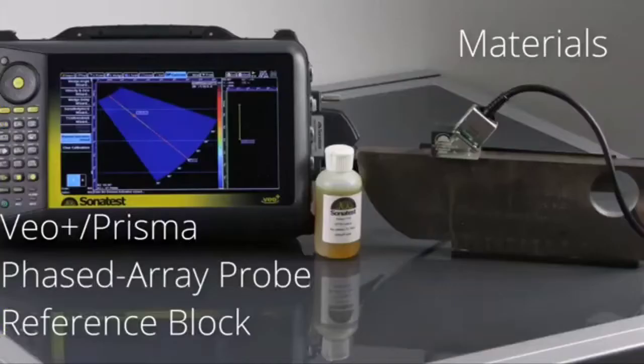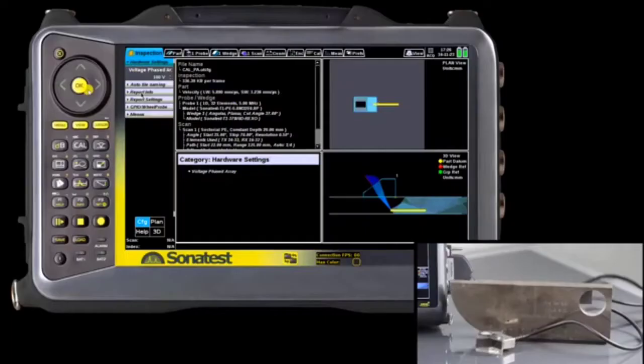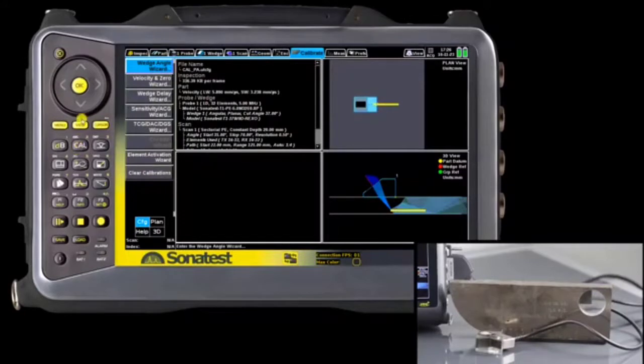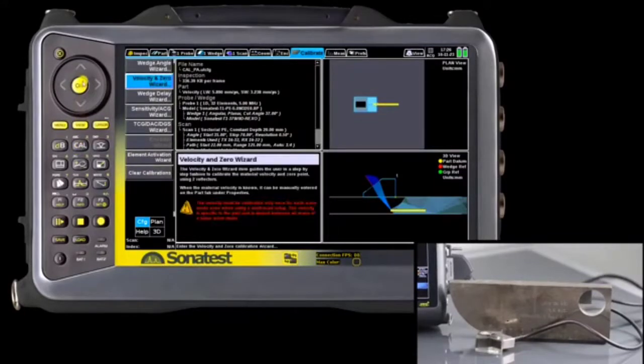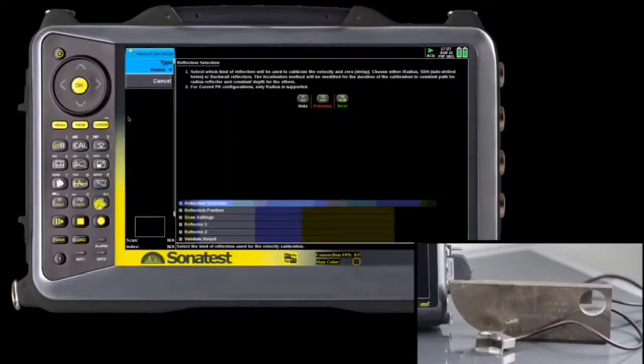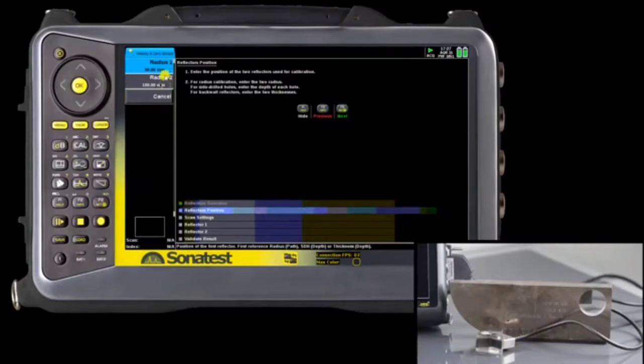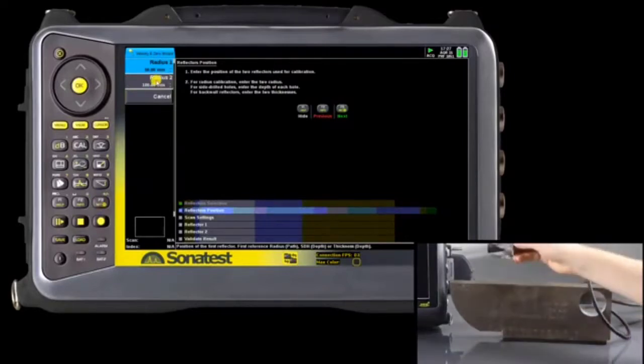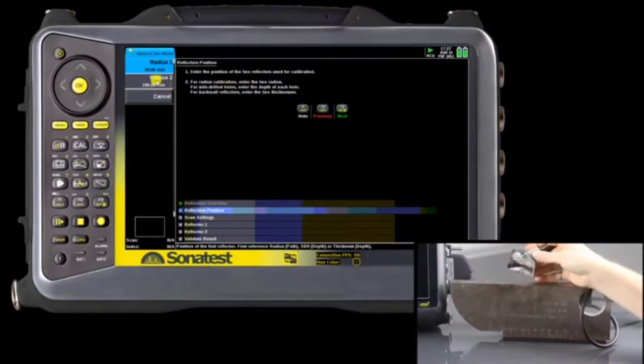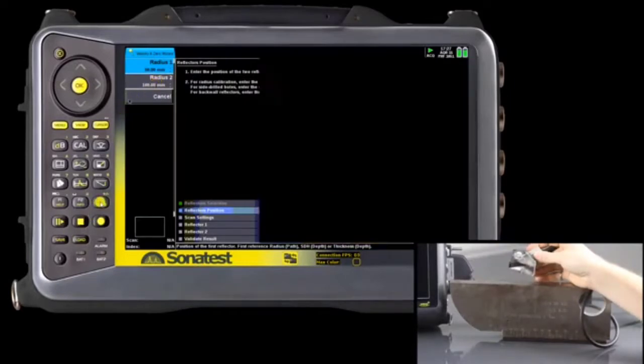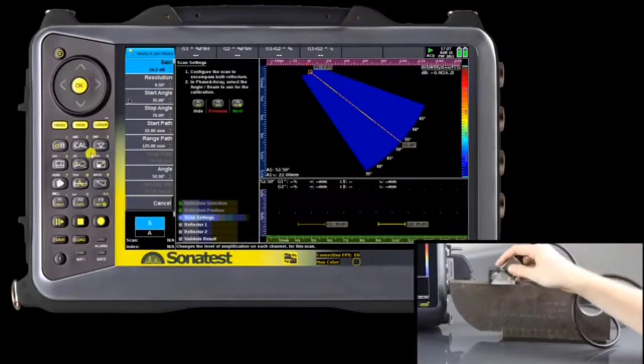For this calibration, you're going to need a VEO Plus or Prisma instrument, a phased array probe and a reference block. We are using the same setup as in the previous video and are going directly into the velocity and zero wizard. For the reference type, please select the specific radius to match your calibration block. Make sure to enter the good value of the reference radius. On the screen, you should normally see 2 echoes from both reference radii.